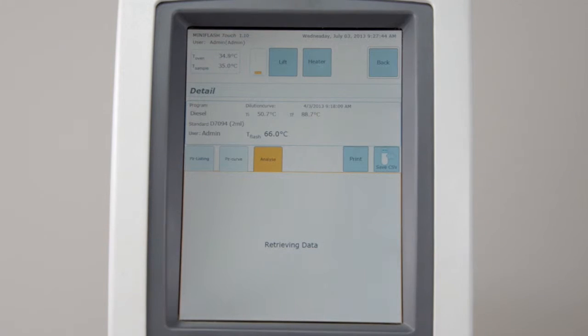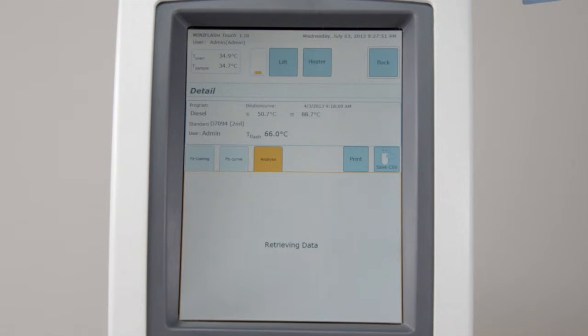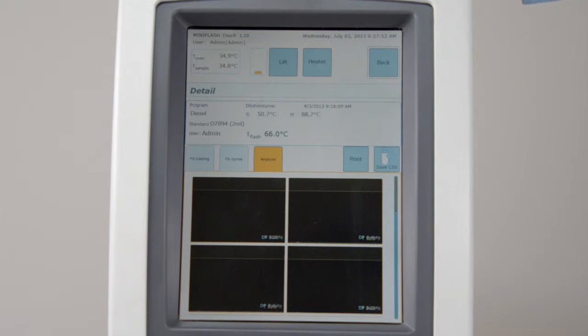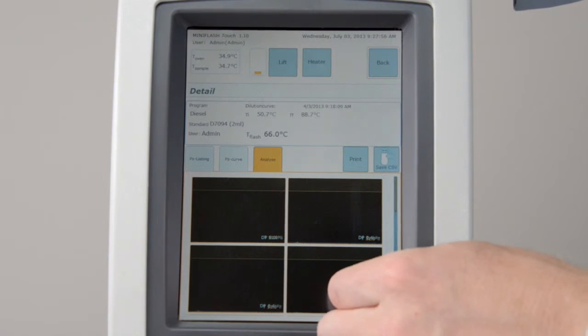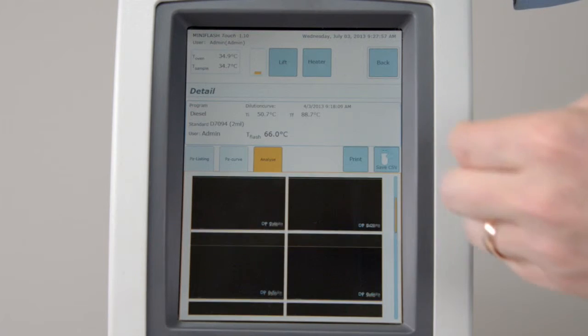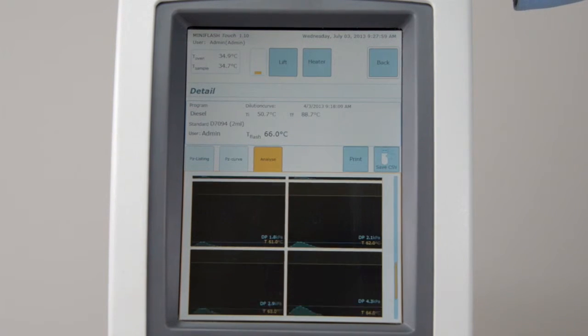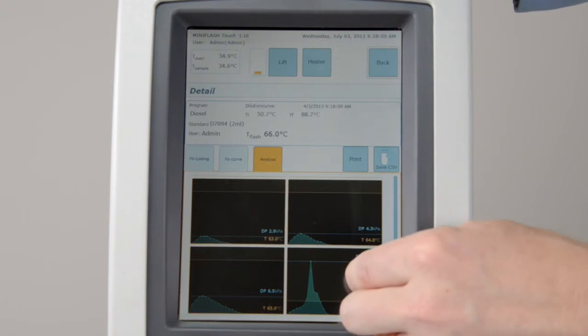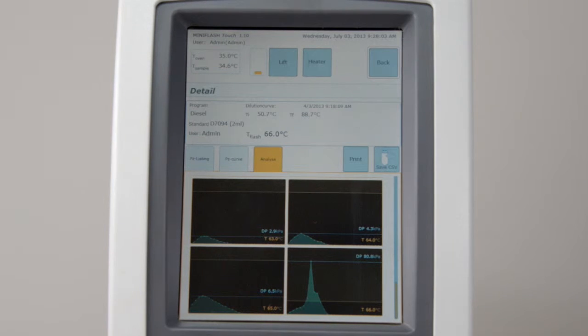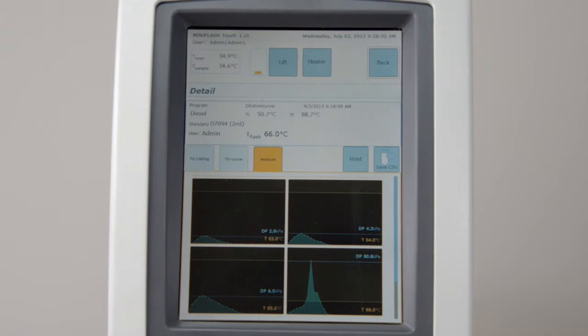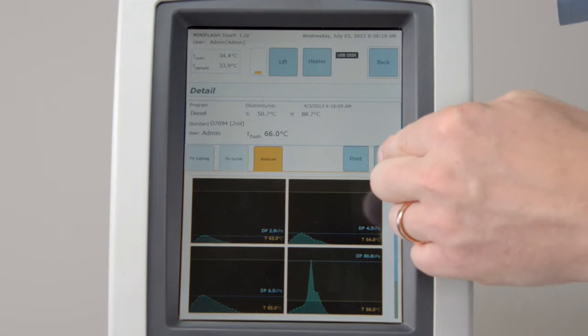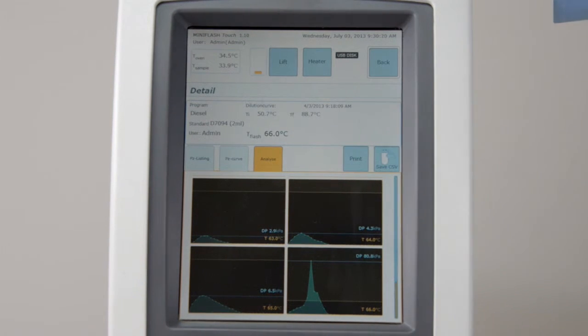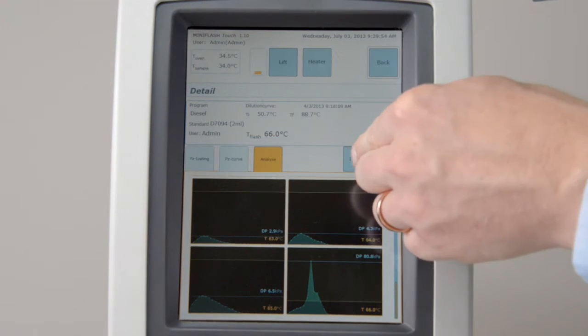Select the Analysis tab to generate combustion profiles from the data. Generating profiles may take a while. Scroll to the very end to check the profile when the flash point was reached. For a pure and clean substance, this profile must be pointy and narrow, indicating a high ignition quality. You can download the result and print the profiles from this screen.